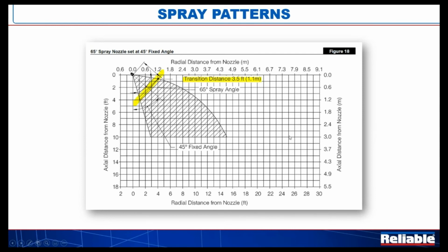That yellow line you can see is what we call the transition distance. It's in this case 3.5 feet before gravity grabs it and starts curving that water downward. And we've set all of these, the coverage at the bottom of these, at 10 feet off the floor. What's happening at that point? Everything's going vertical. Would there be a need to set this 18, 20 feet off the floor? Not likely, right? So you're typically going to be having your asset protected within that hatched area right there.